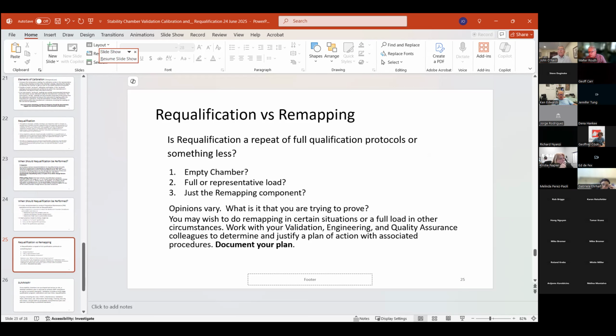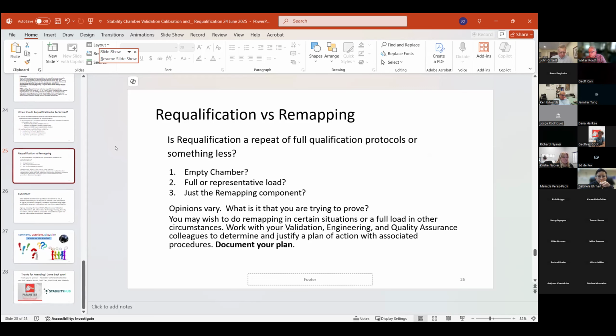My experience has been it's typically performed in an as-found capacity, which is already loaded, and if you're half full at that time, you don't need to load 30% more to get to 80% or something. We just define our requalification as as-found. That is also what I see, Walter, as well. And something that I see often that may be a little counterintuitive is typically a loaded mapping is an easier mapping than an empty mapping.